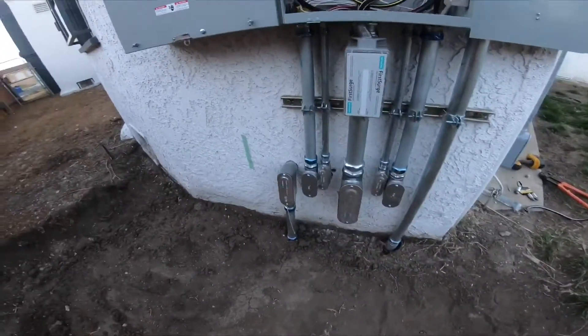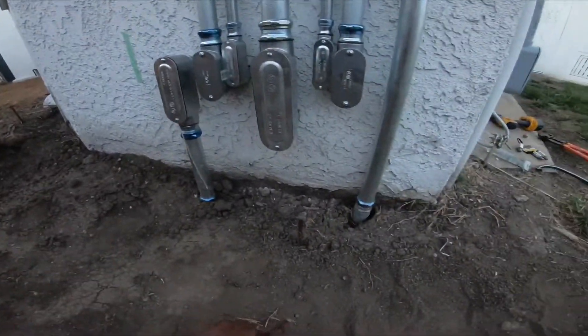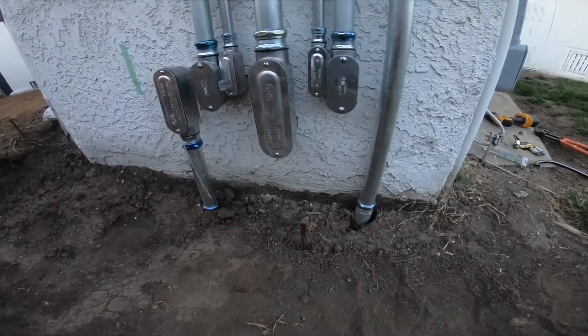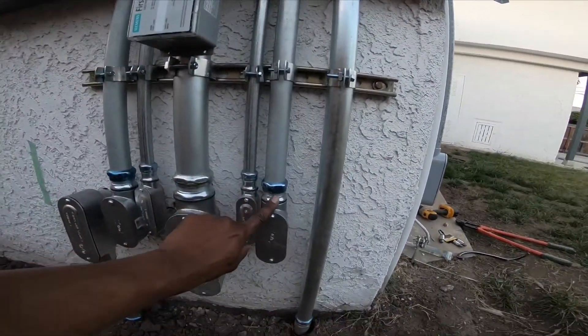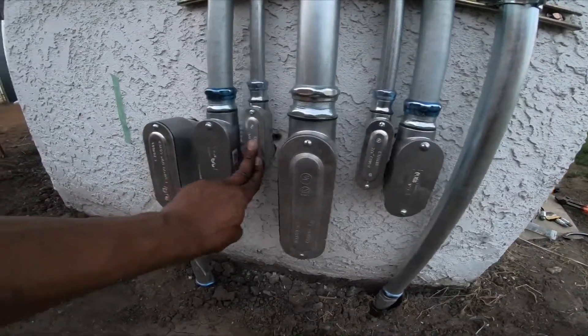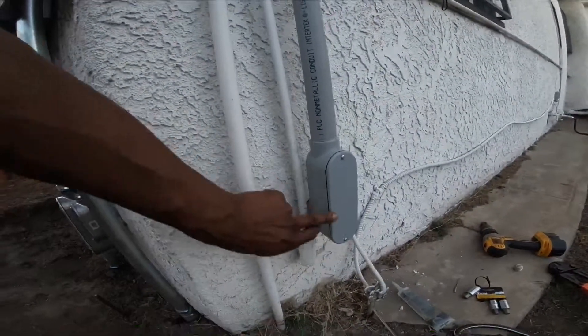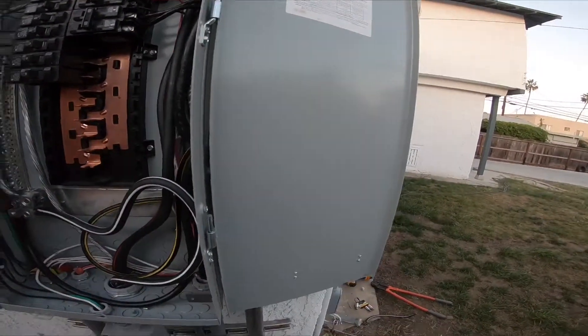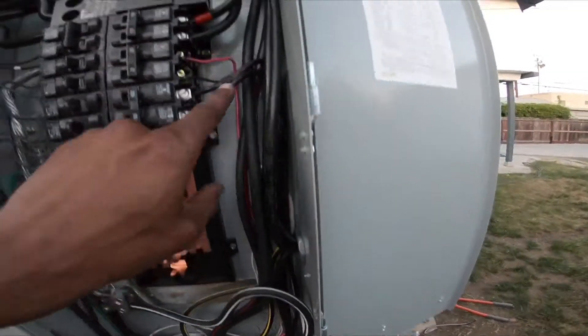Comes up here. I've got two rods. One here. One there. I have the clamp for the rods, but I didn't get the wire. I'm going to go with four gauge. Just because. I'll come back. Tighten all of this. I'm just feeding this one through. Make my connections. Live. I'm back feeding everything on copper coming up to these two here.